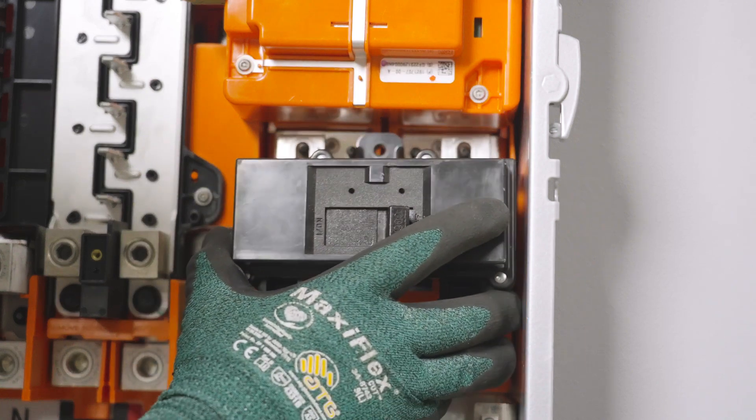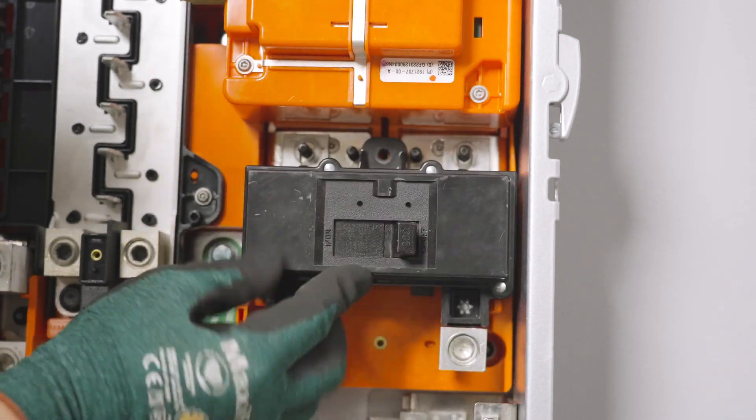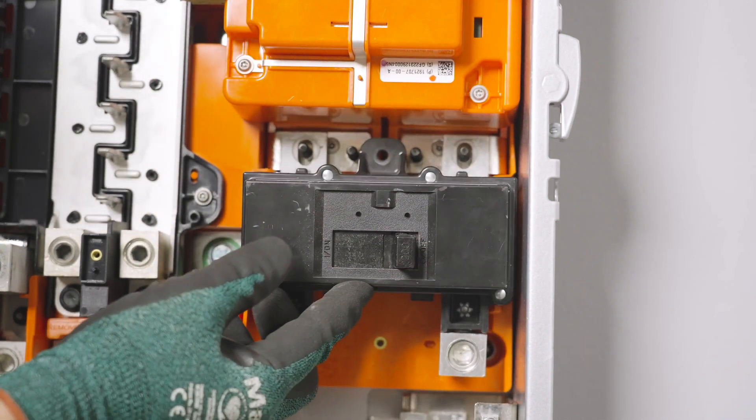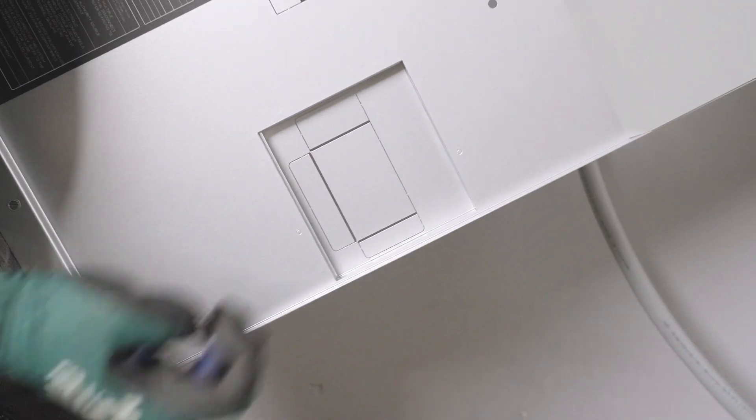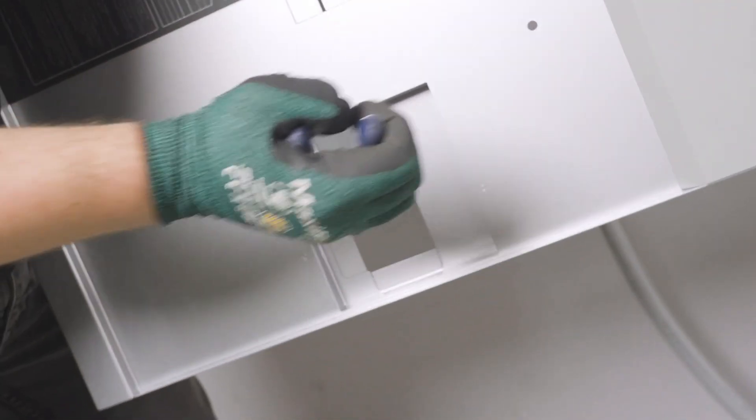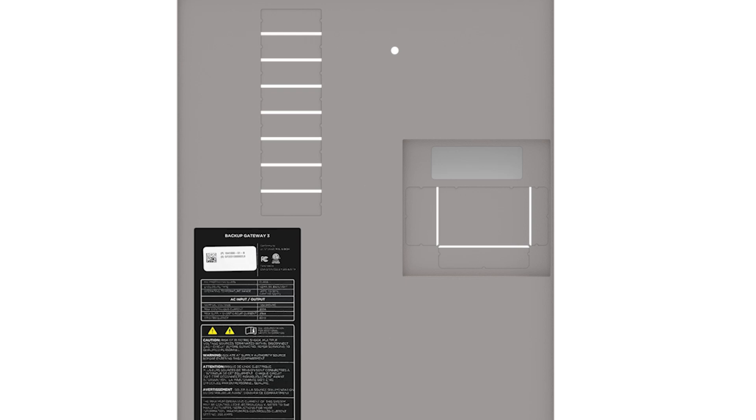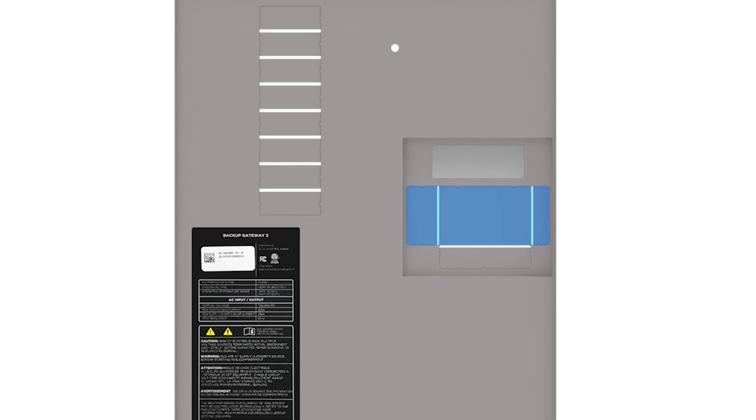Please note, Square D main breakers require an accessory hold-down bracket which can be ordered through Tesla. Finally, remove the main breaker blanks on the front cover. Square D main breakers require removal of these three blanks, while Eaton main breakers require removal of these two blanks.